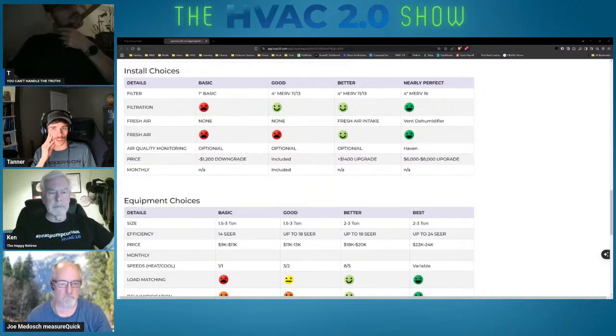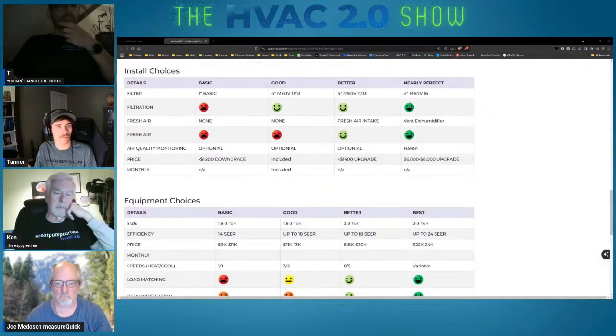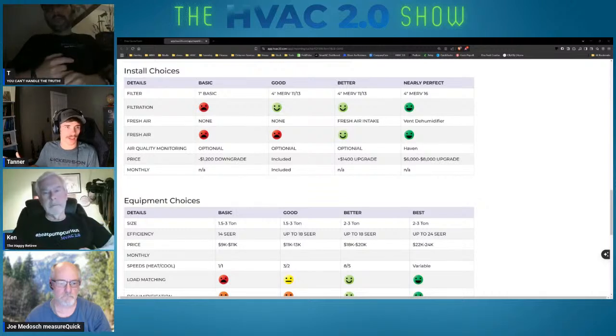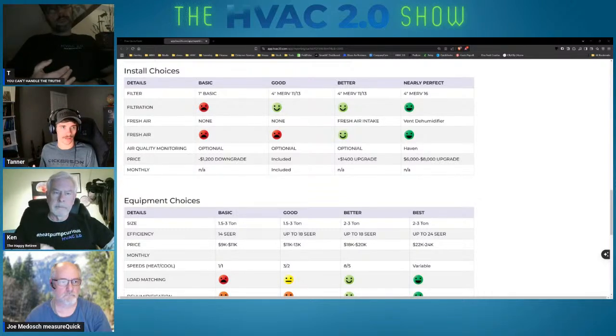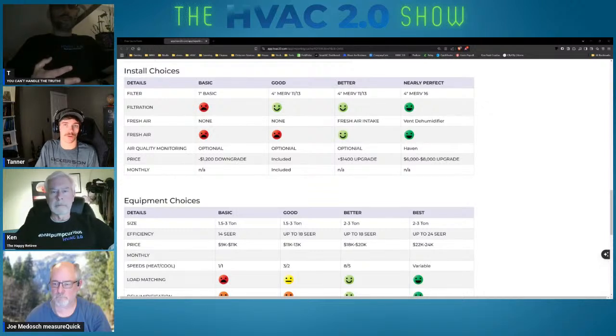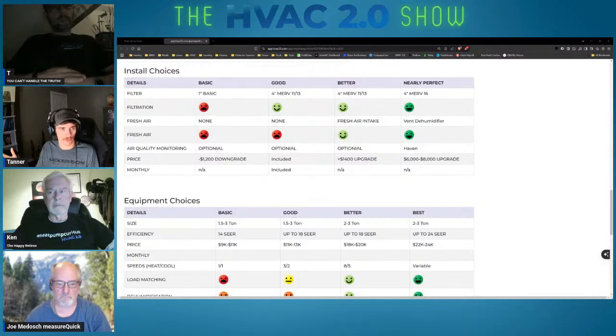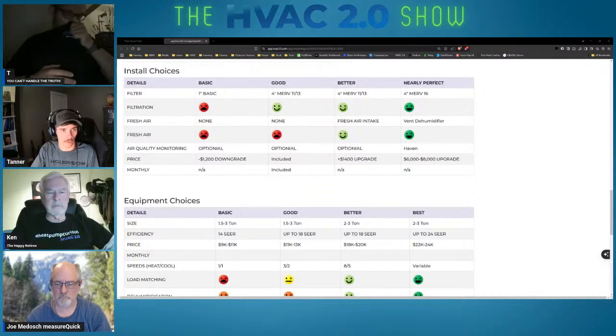In those scenarios, I would probably lean towards saying, you know, you have 2.5 tons of duct here, sir. We don't really know because your system's currently broke, but based on what I've seen previously, here's what it's kind of looking like. You can lean into this likely load range, and if we're not doing a comfort consult, we're going to be making some form of assumptions to some degree. So if we're going to make assumptions, just know here is our safe zone and here are our risky zones. If we go back with another 4-ton for this 2,000 square foot house, we are in the higher risk zone where starting up this brand new system could peg out our static pressure. If that's the case, we're going to be looking at new ductwork. Do we want to replace all that ductwork now, or look at sizing more into the less risky zone?